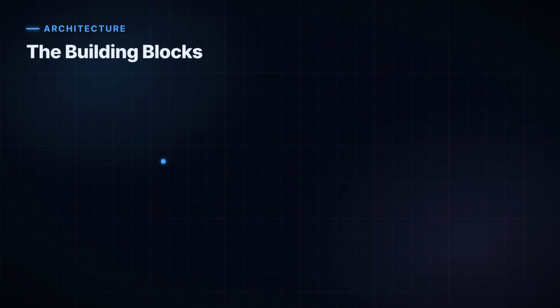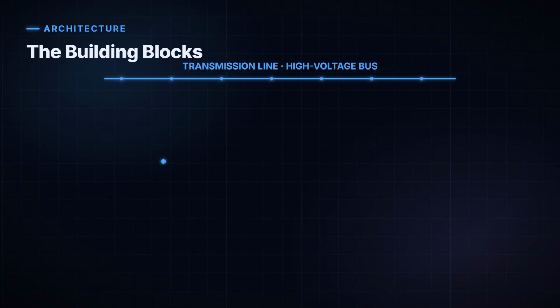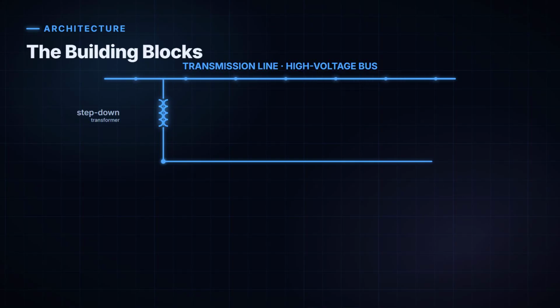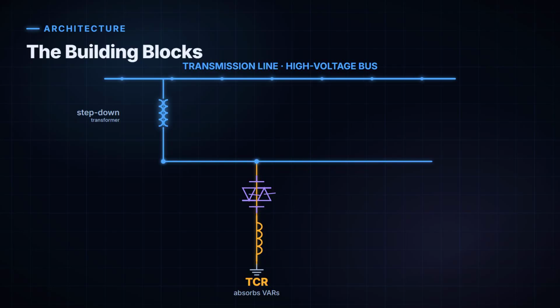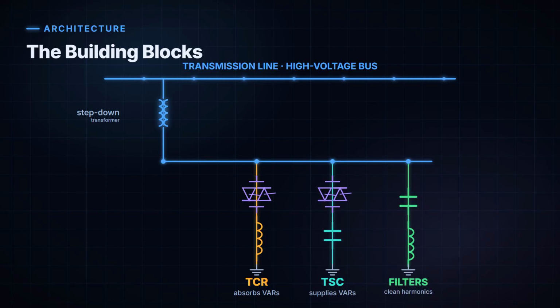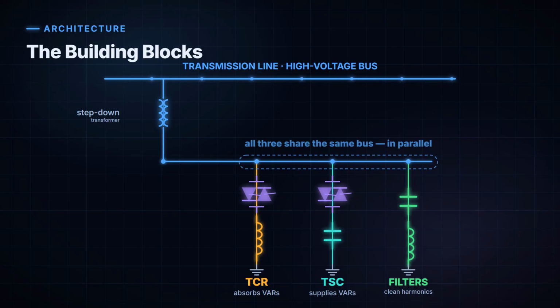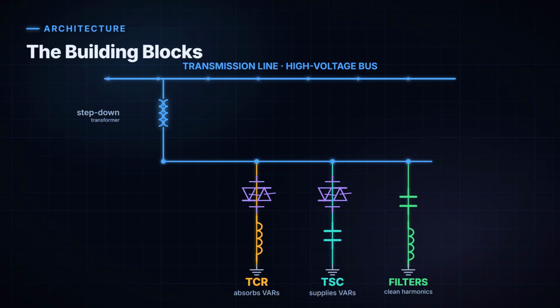Now let's build one. We'll start at the transmission line. That's the high voltage bus we want to protect. We connect our SVC to it through a step-down transformer, because the electronics work at a more manageable medium voltage. And then, hanging off that connection, we have three building blocks working as a team. First, a thyristor-controlled reactor, which absorbs reactive power. Second, a thyristor switched capacitor, which supplies it. And third, a set of harmonic filters. Watch how each one connects in parallel. They all share the same bus. Let's take them one at a time, starting with the reactor.